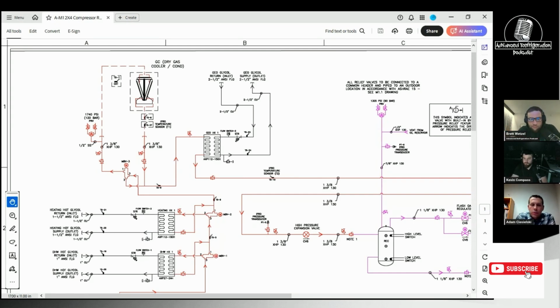Yeah, it's important. What I was referring to as far as our goal is to slow down the fan reaction, right? That is key to complete system stability. If you got fans erratic, then the high pressure valve and flash gas valve are going to be erratic. Your receiver pressure is bad. You're feeding your expansion valves with poor liquid quality and varying pressures, and it just ripples right through the whole system. If you lock your fans in tight with tight control, that certainly helps give the opportunity to the downstream control devices to do their job.